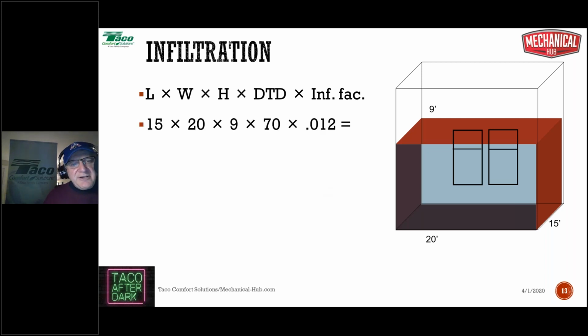If you got a calculator, gotta play along at home, gang. 15 times 20 times 9 times 70 - that's our design temperature difference - times the infac of 0.012. Multiply that out in a string, and that will give us an infiltration heat loss of 2,268 BTUs under design conditions. All right, so that's infiltration heat loss.